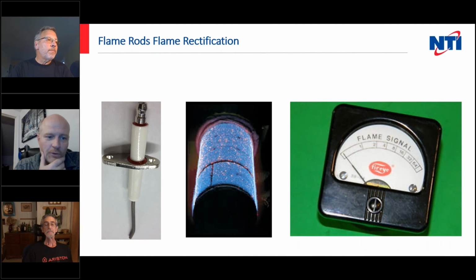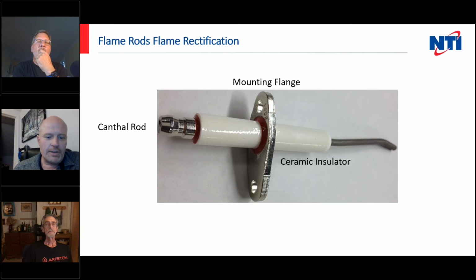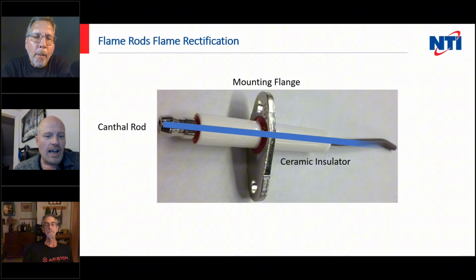Okay, we're going to talk a little bit about flame rods and flame rectification. All right, guys, this is your basic flame rod. It basically consists of 3 parts. You've got a mounting flange, a Kanthal, which is the metal that this rod is made out of, and this rod runs continuously from top to bottom.